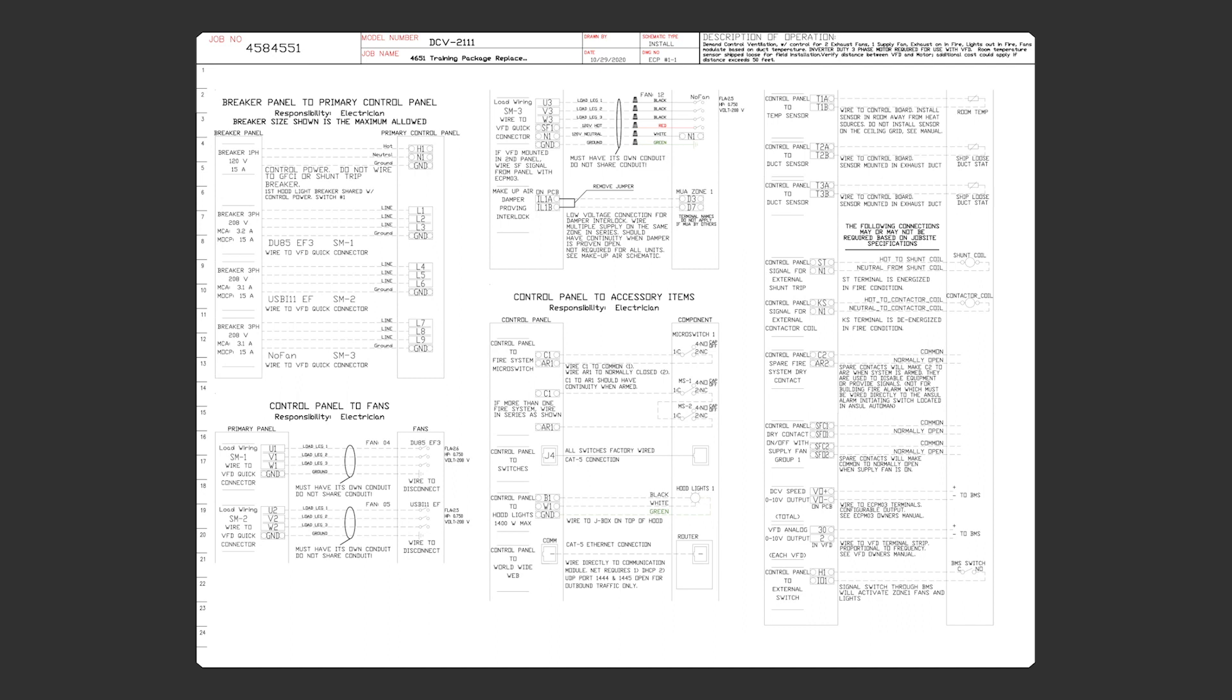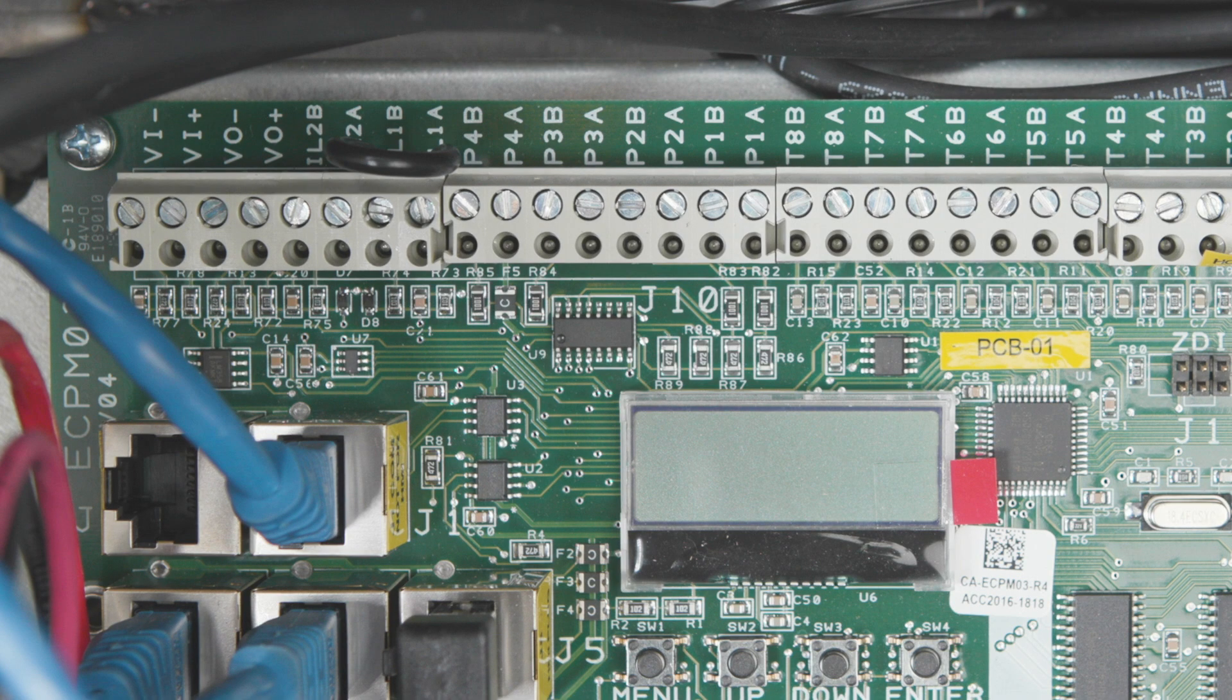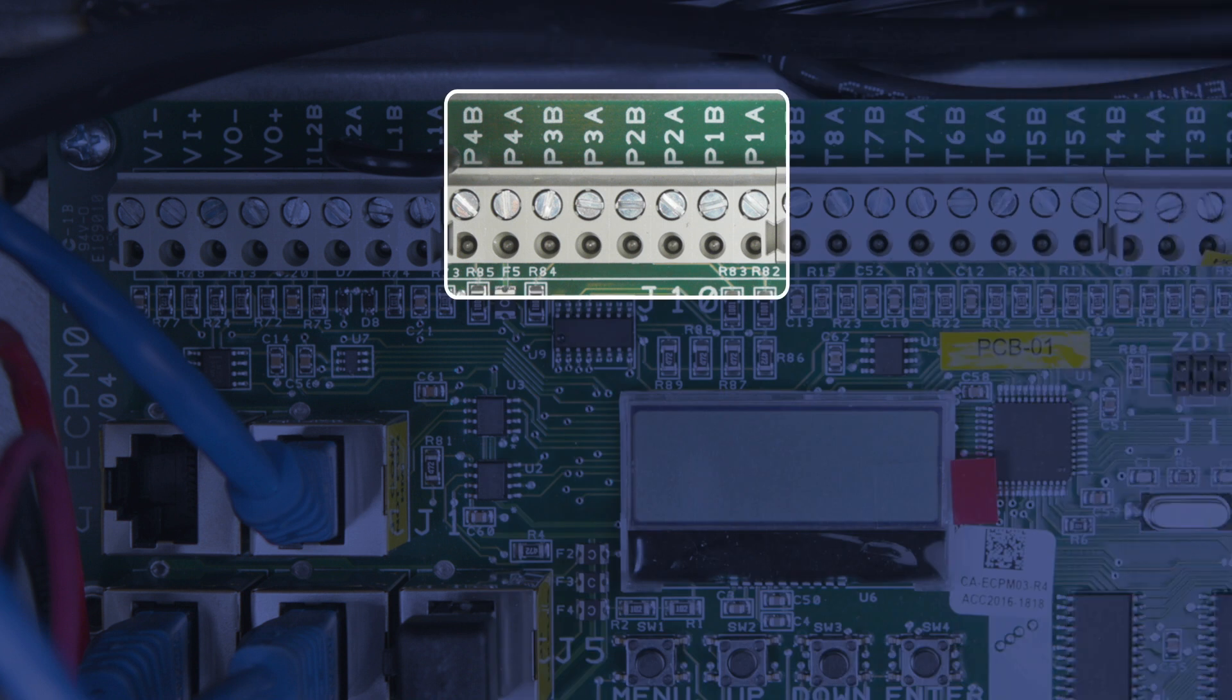Solid lines are factory-wired for you, and dashed lines will require field wiring. One specific note on wiring EC motors to our circuit board is note that the P terminals shown here are polarity-sensitive. So double-check this before applying power. Reversing polarity will damage the terminals.